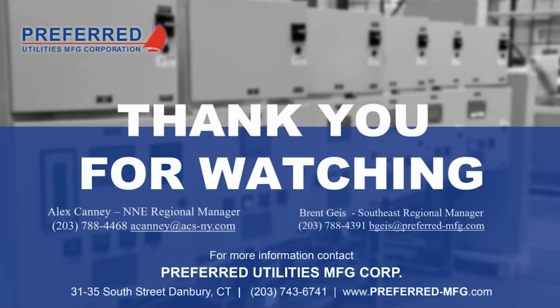Yeah, so I'm seeing a lot of that, Alex. There's a lot of older tanks out there. When you start thinking about sizes of tanks in general, usually you find that they're limited to about 50,000 gallons, especially underground. And that's because that's about the largest that you can easily transport without field erecting or field welding parts of the tank together in the field.